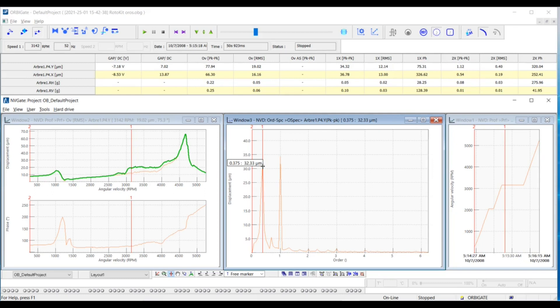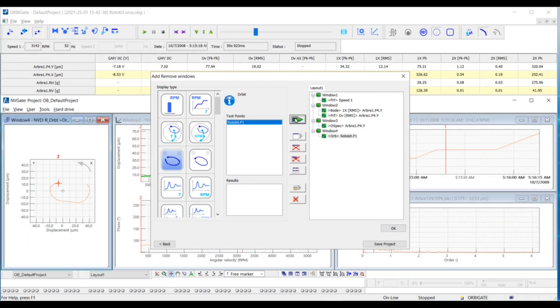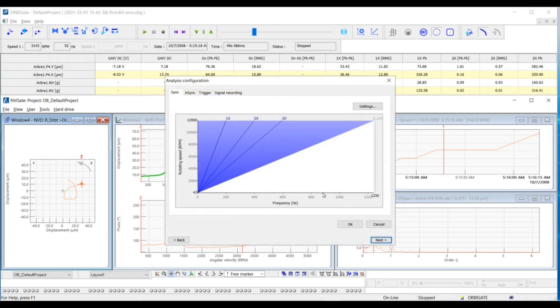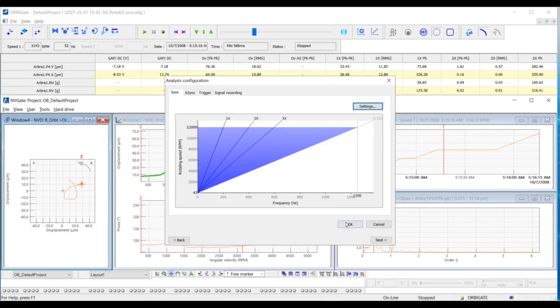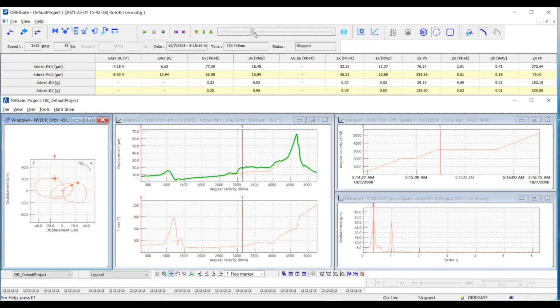I will display the orbits to check for oil instability and will make a report to send to my team. To do this, I will add my whole orbit. You can see that this orbit is not closed — you will need more than one orbit in order to close a cycle. At 0.375, I need roughly 3 revolutions to complete one full cycle. I can easily go through the analysis tab settings and display 3 revolutions rather than 1 — I do not need to play back the signal, I simply ask the software to display more. We can now see the orbit is closed.